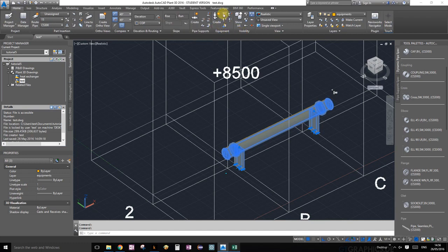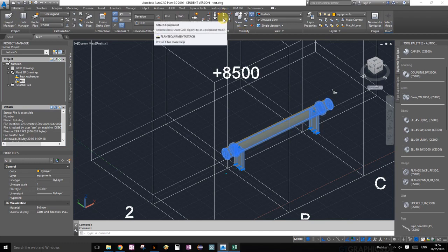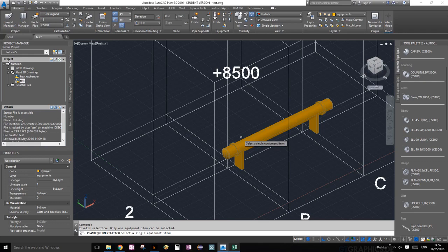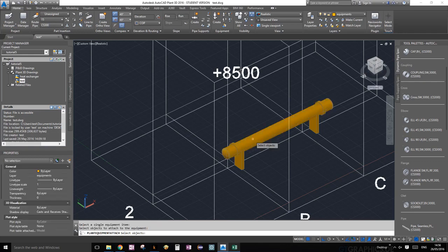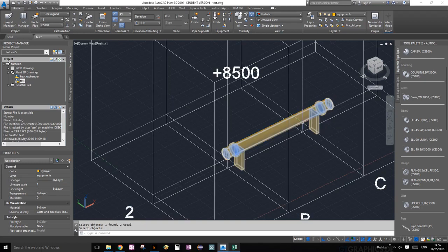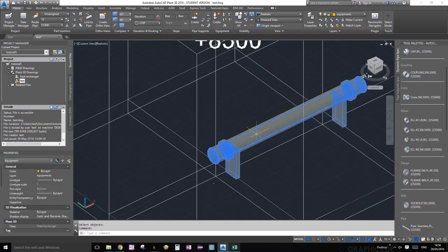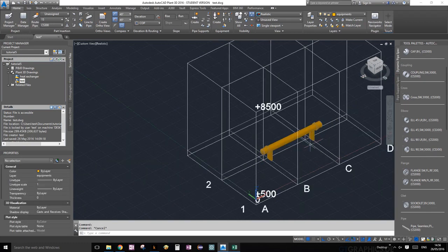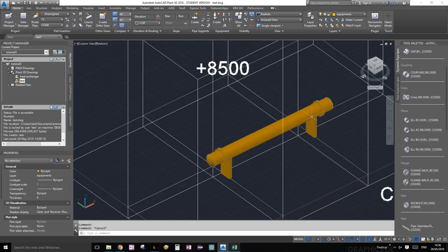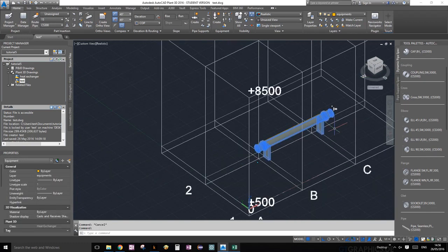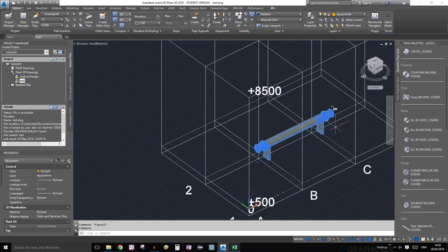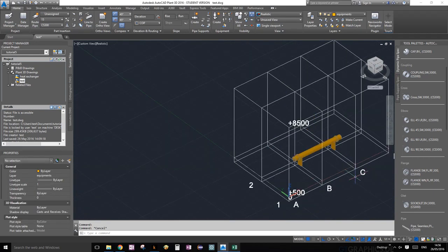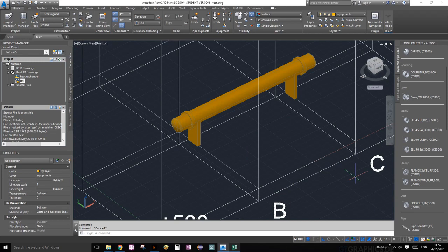Now one thing we need to do: these are just objects right now, the heat exchanger and the supports, but we want to identify the entire thing as our equipment. So go ahead and select all your equipment. We're going to select the two support boxes and our heat exchanger. And under Home, go to the Equipment palette, not Modify. It says Attach Equipment. We're going to click on Attach. It's going to say select a single equipment item, so select that one, select this, select this, press enter. That's it. Now as you can see, our equipment is here. Do we have a tag? Yep, we still have a tag. So perfect. Now our whole thing is recognized as equipment.